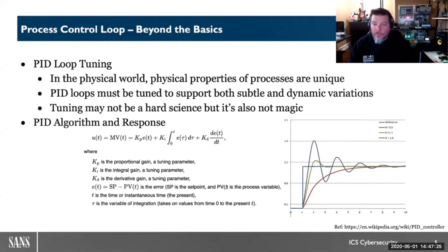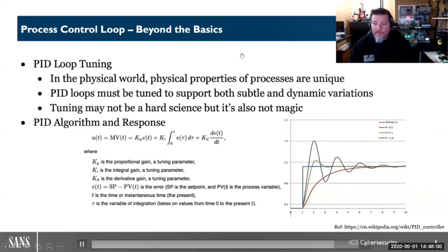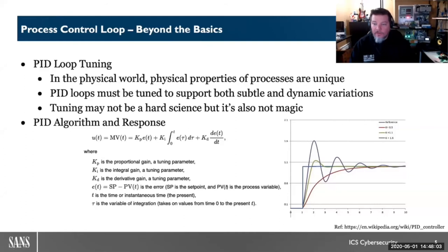As systems become more complex, so do the PID loops used to operate them. We may have a very tight system requiring a fast response time, because if we are too hesitant in bringing it to the appropriate temperature, it could cause a quality problem with the product. We must tune the loop using the physical properties of how the system was designed in order to come up with the appropriate response curve and avoid overshooting and oscillation.